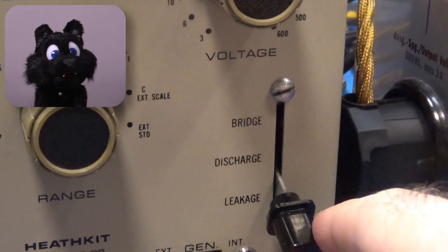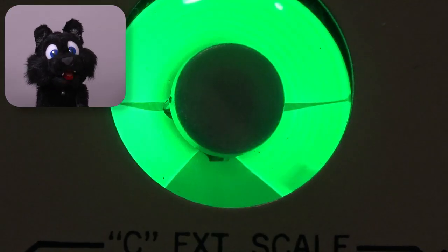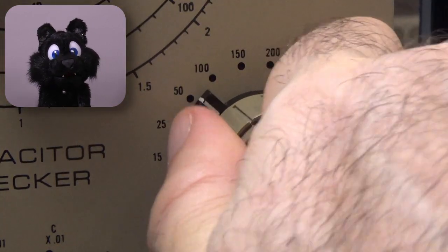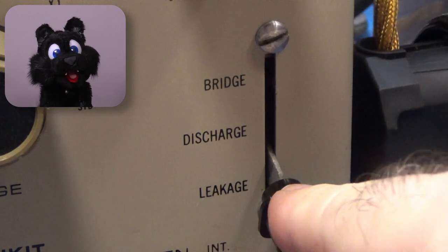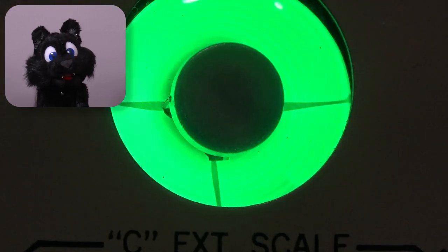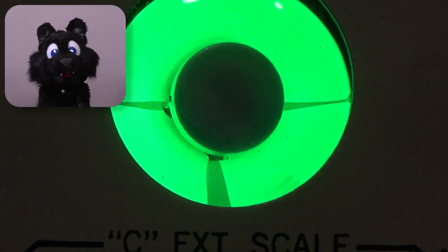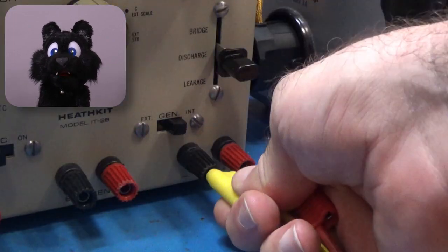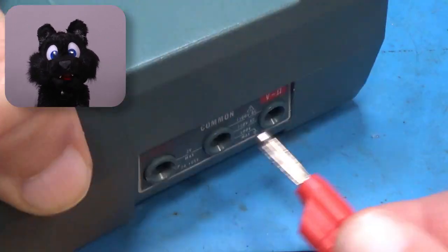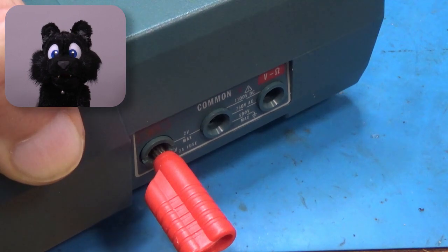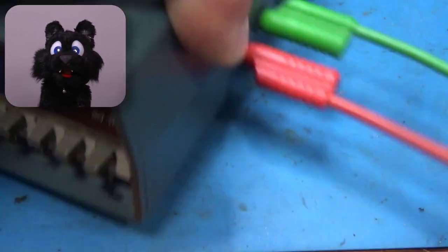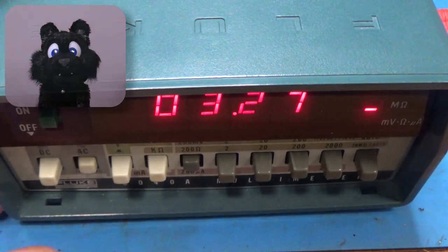If everything works out, the eye-tube should open up completely after a short burst of charge time. If it doesn't, there is leakage current. Plain and simple. The adjustments are quite accurate. The paper mode detects currents of only 2 microamps as faulty, at any voltage. The electrolytics is satisfied with 2 milliamps.